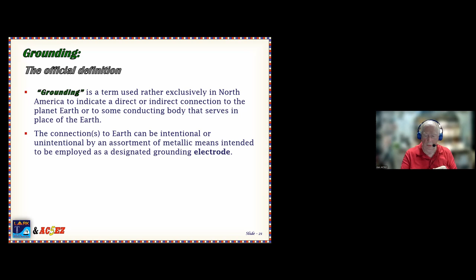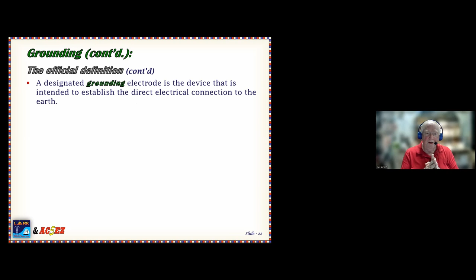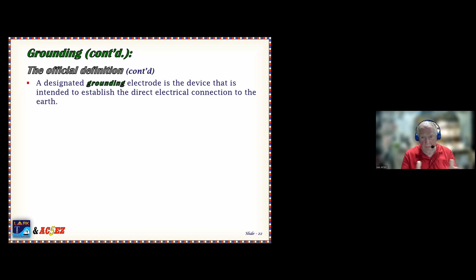Most of us have driven copper rods into the ground. So a grounding electrode, okay? A designated grounding electrode is that device that is intended to establish the direct electrical connection to Earth. Now, a lot of houses built from about 2000 on, when they wired the houses, they wire your circuit breaker box to either a ground in the slab, or they drive an 8-foot ground rod right at the circuit where your meter is usually. So either you have a wire going back into your foundation, or you have a metal rod out there somewhere. That's how they ground your house.